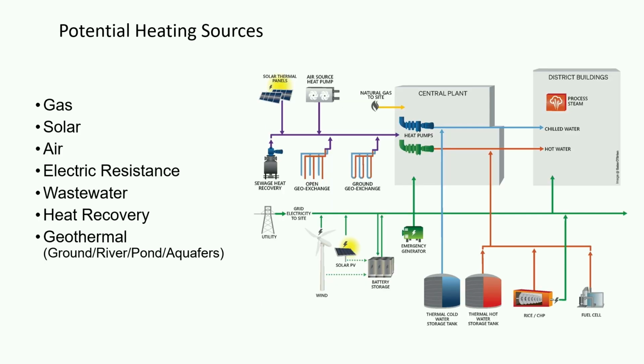So again, we mentioned the potential heating sources. There's a lot of different opportunities here. We mentioned wastewater. Obviously, electric resistance is really not a good idea. But we do have some air source opportunities now. Manufacturers are really starting to develop large tonnage air-to-water heat pumps that can help with domestic water and/or supplement the geothermal system as a hybrid. So we've got a lot of opportunity. We've also got thermal storage. And there's some great PV and solar systems out there that you can put on the facade. There's the different electronic shading, like View glass, where you can really impact the cooling load from the glass perspective. So there's a lot of different technologies that can really help that load profile become balanced, which is what Sam's going to talk about at the end, because that's extremely important for the long-term net effects of the bore field.